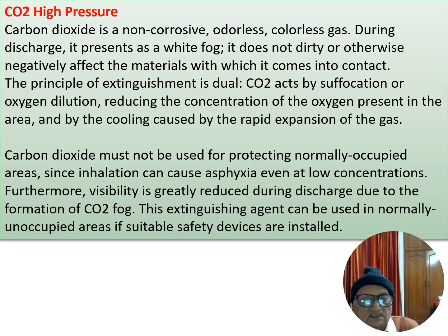CO2 acts by suffocation or oxygen dilution, reducing the concentration of oxygen present in the area, and also cooling is caused due to rapid expansion of the gas.